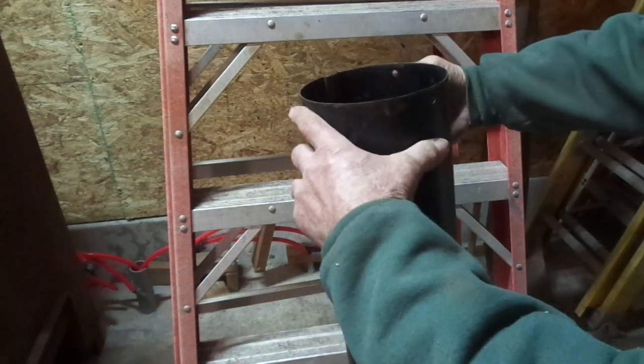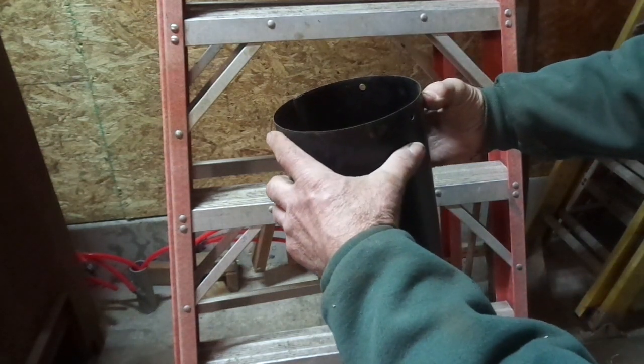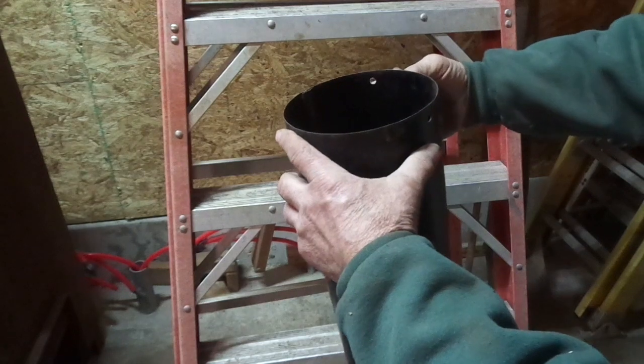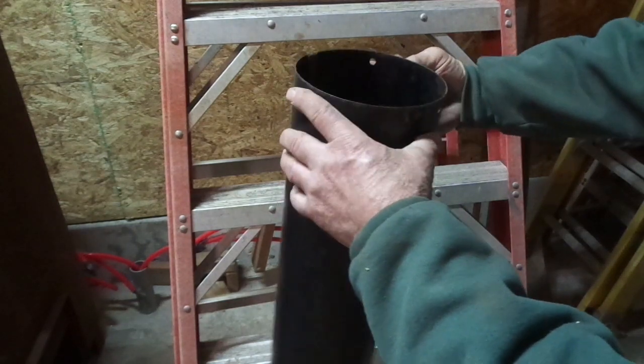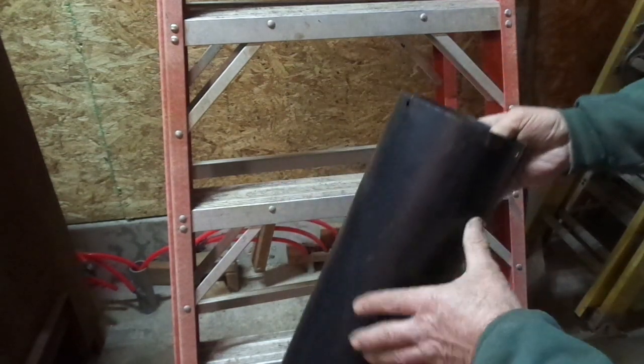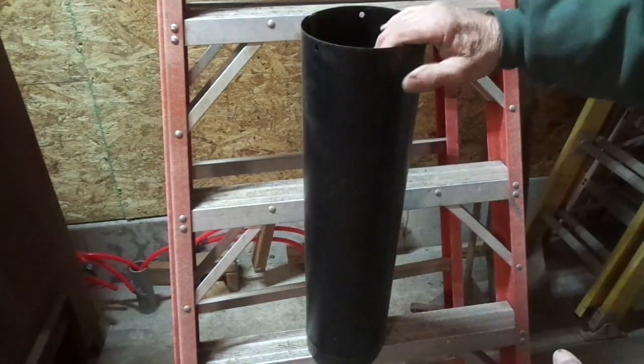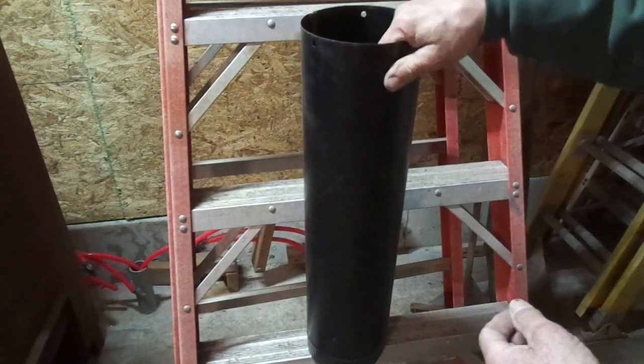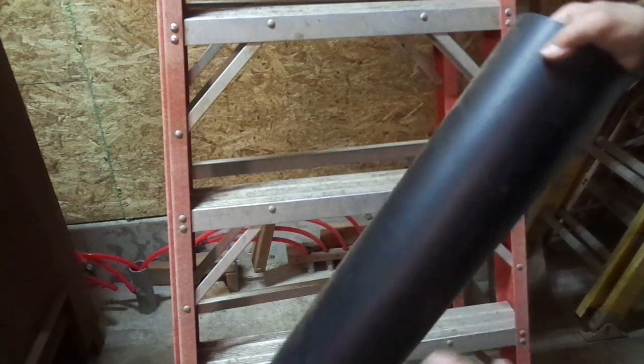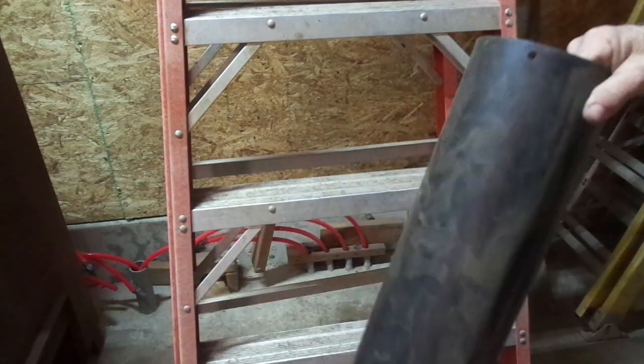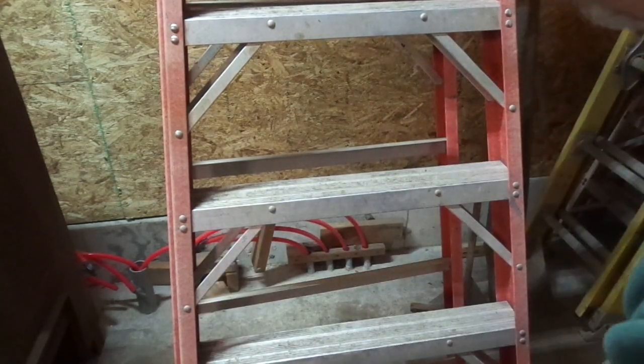If you just put 2 of them in haphazard, especially across from each other or just even partially across from each other, that flue will actually move back and forth with the volatility of that explosive flue fire, and it could actually come apart and give you somewhat of an issue, give you a real bad day. So generally speaking, always 3 screws 120 degrees apart.